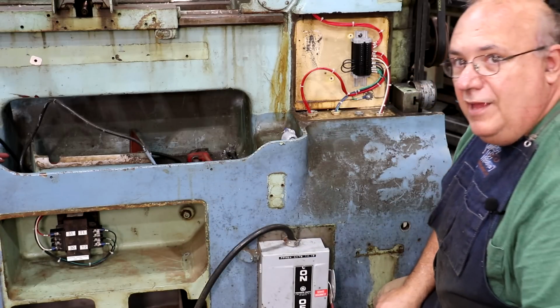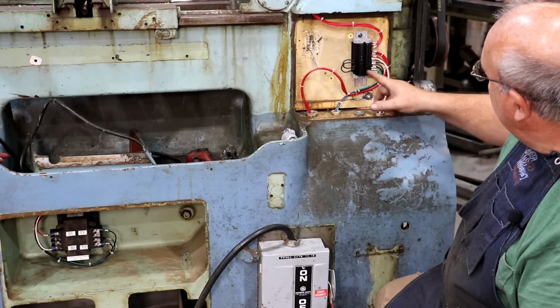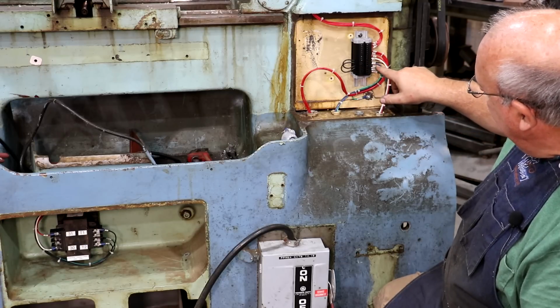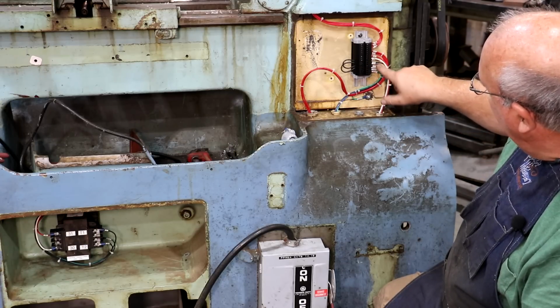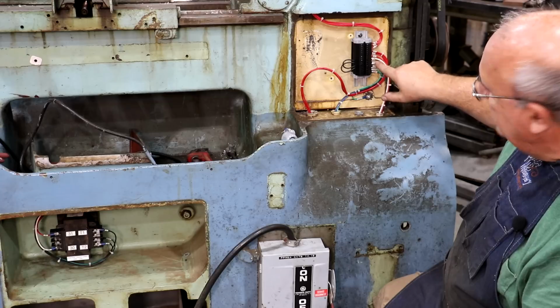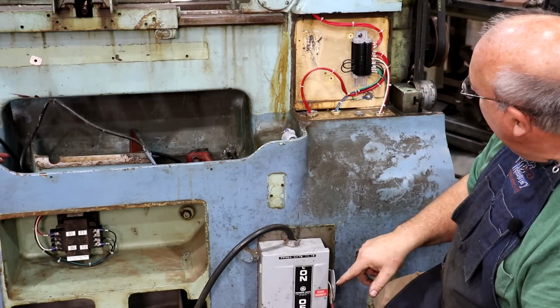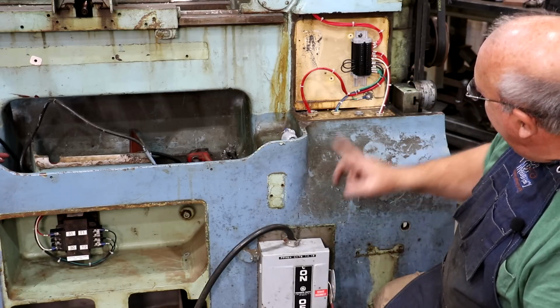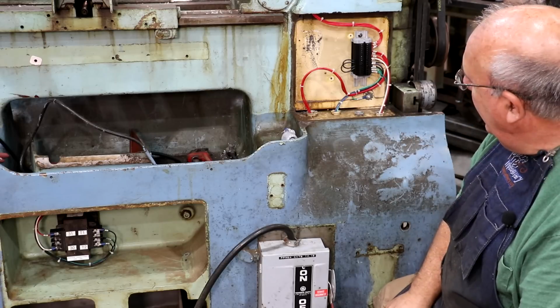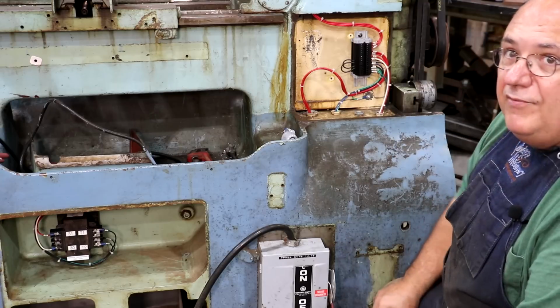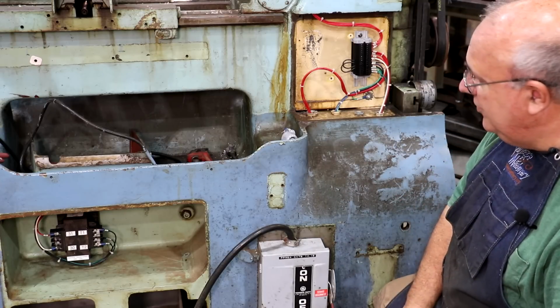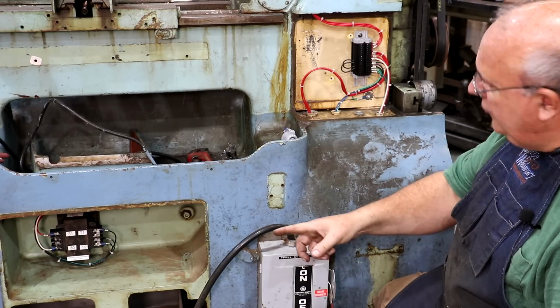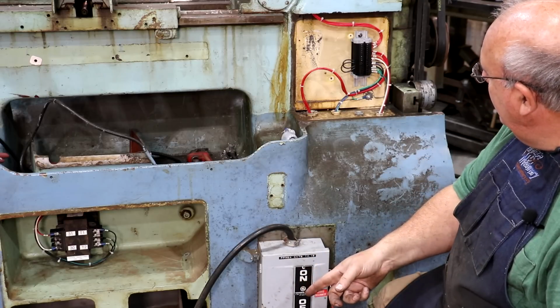I came in here and put some jumpers from my hot lines coming in, the L1, L2, over to the T1, T2 that go to the transformer, and powered it up and came over here with my meter and checked everything out. And sure enough, everything is working like it should now. So we have a control transformer, and it's been checked out. Everything is good there.